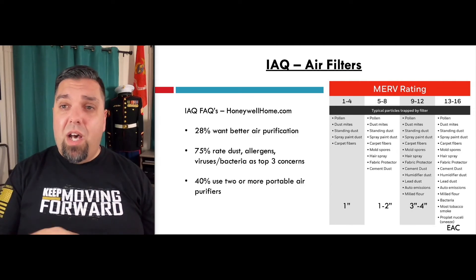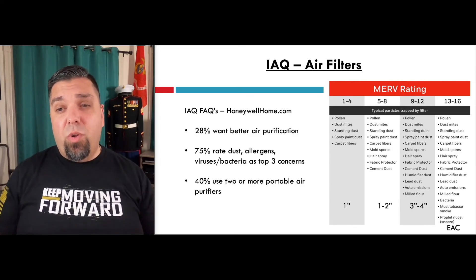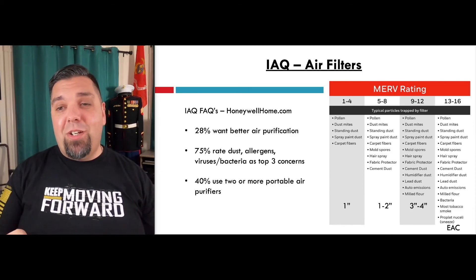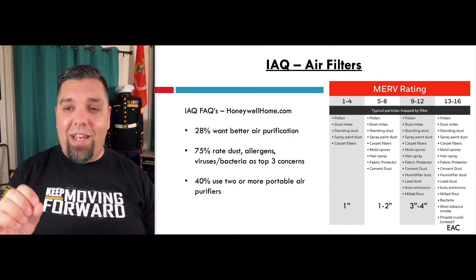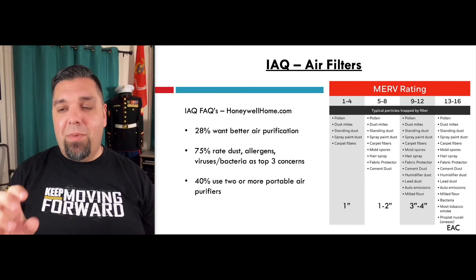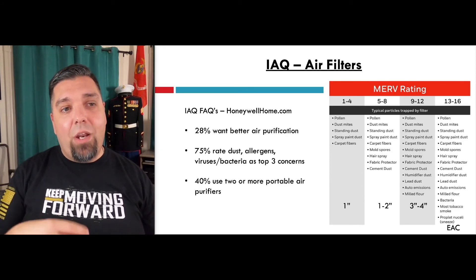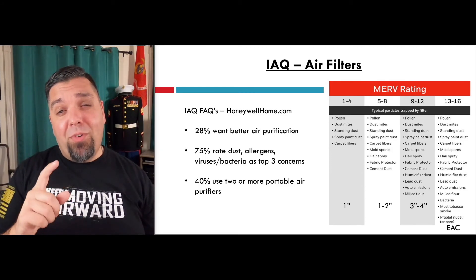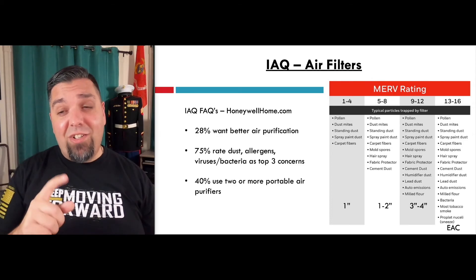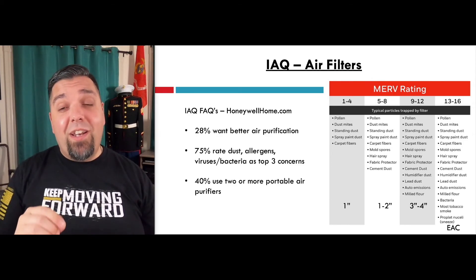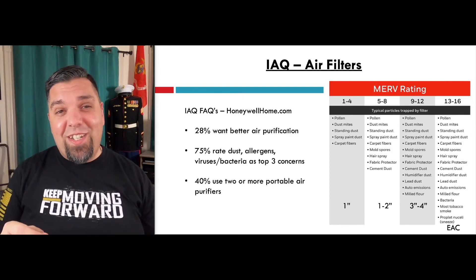Keep in mind: the higher the MERV rating, the bigger the pleats or the more electronic you're getting. Make sure there's a rating confirming no ozone is added — some electronic air cleaners, especially older ones, may add ozone to the air. I found out the hard way: some people are actually allergic to ozone. I put in an electronic air cleaner once and it made their allergies worse. So you have to ask what they're allergic to.